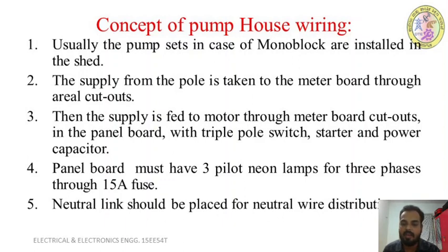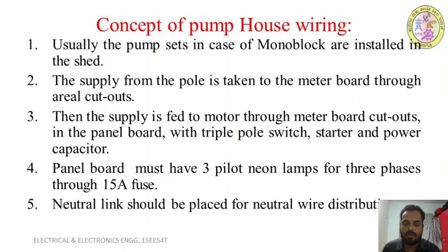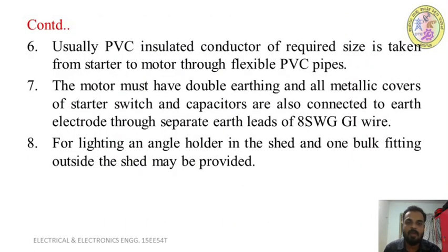The panel board must have three pilot neon lamps for the three phases (R, Y, B) through 15-ampere fuse units. A neutral link should be placed for neutral wire distribution for all lighting installation purposes. PVC insulated conductors of the required size are taken from the starter to the motor through flexible PVC conduit pipe, with a proper cable size selected for the connection.